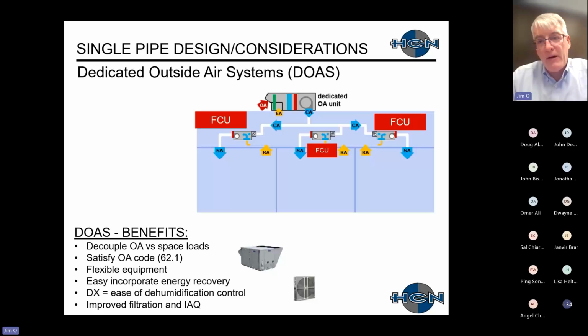And then the other thing to think about is that traditionally these fan coil units, water source heat pumps and stuff like that, were 1-inch filters. That is changing to 2-inch. That is changing from MERV 8 to MERV 13. But traditionally, those fan coils or terminal units don't have much fan oomph, I'll say, to overcome a higher filtration rating on filters, et cetera, where you can easily accomplish that with a dedicated outside air system.